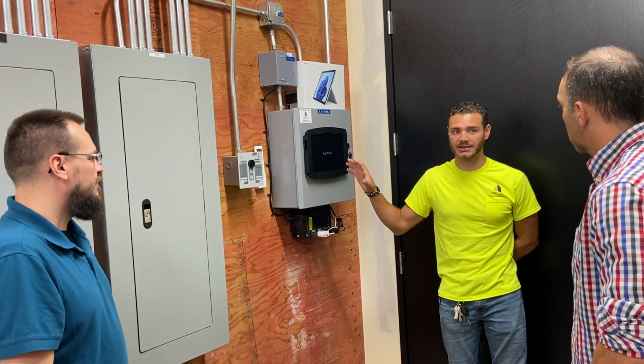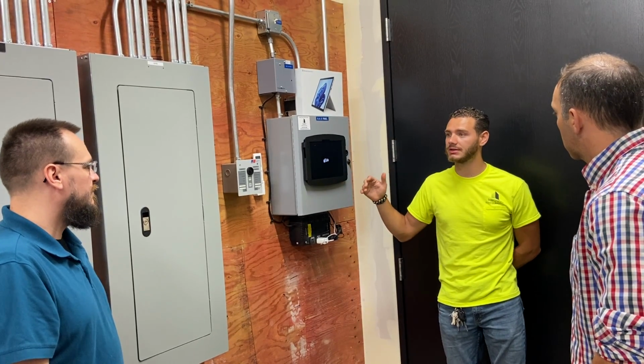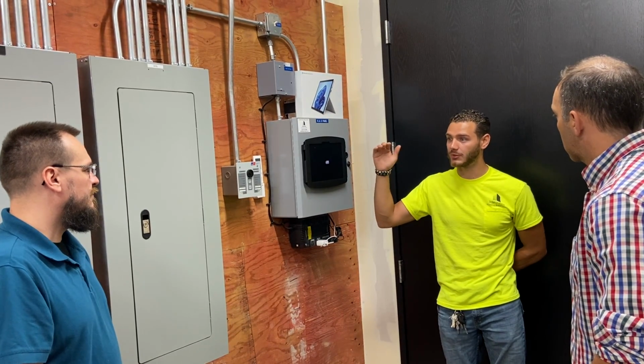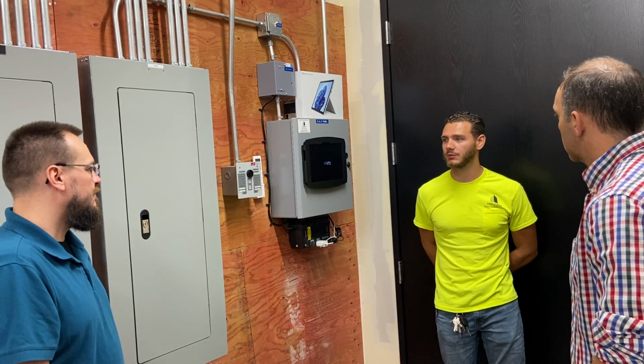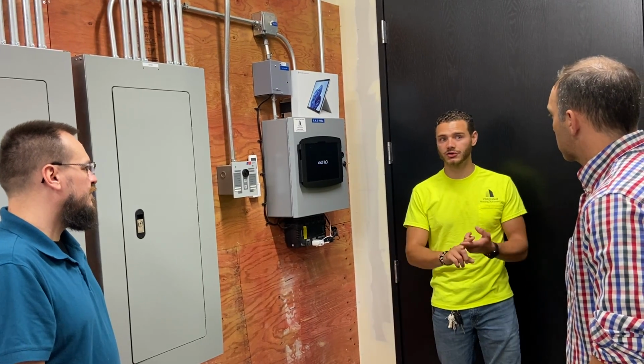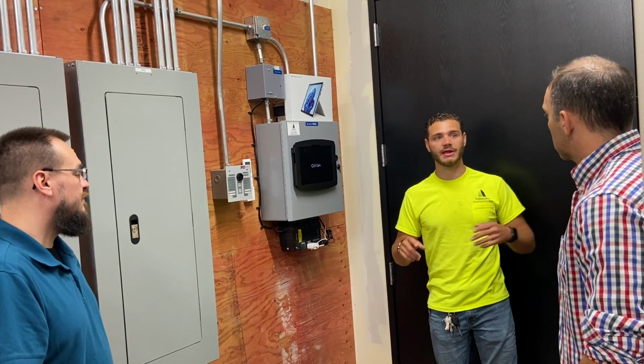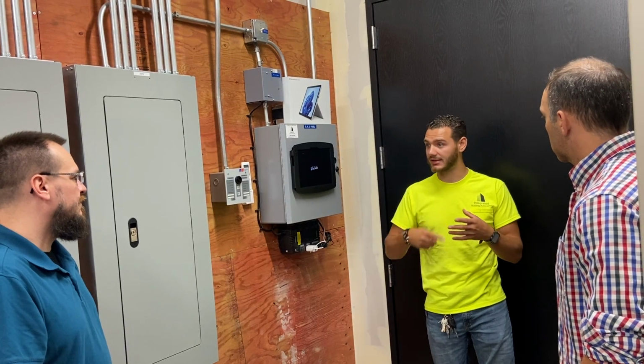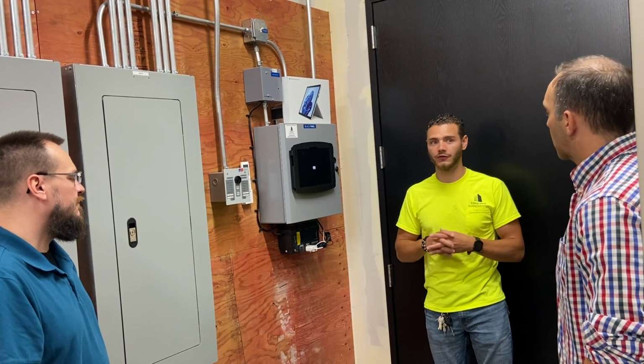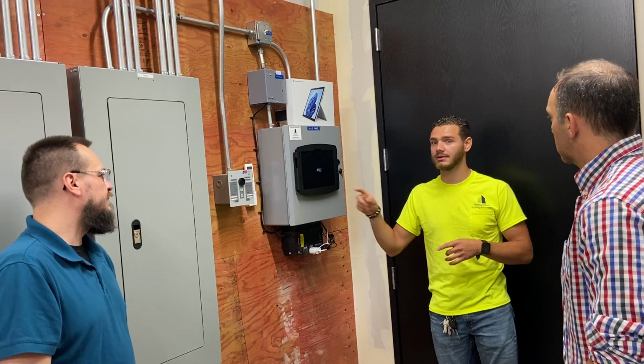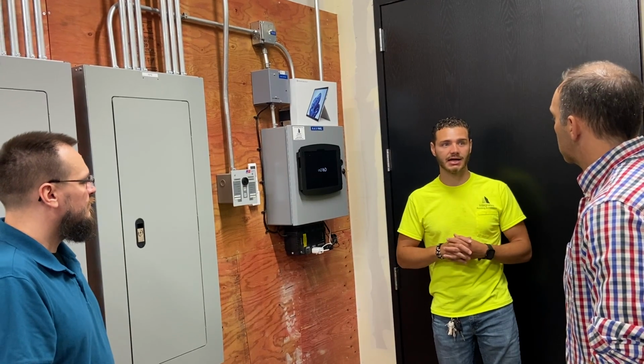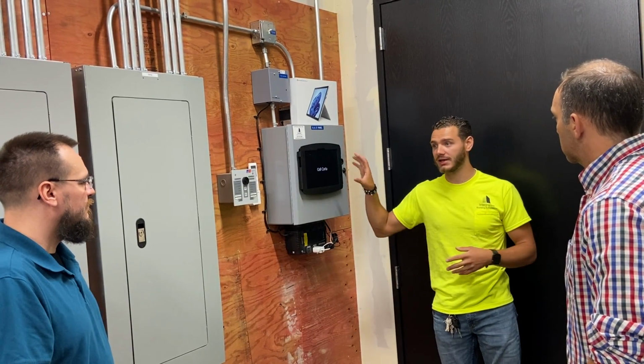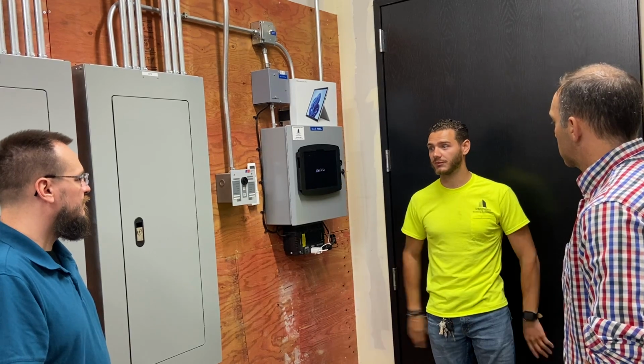It doesn't send you a message. I'm going to show you how to navigate through the screens, and you can reference whether we have any alarms, and there's a couple values we'll want to check. We have transducers on the fans, so we're not going to recognize status until that fan is spinning. So if for some reason we're telling it to command, the breaker's on, everything is on, and the fan's not spinning, I'll be able to tell you the fan's not spinning from right here.